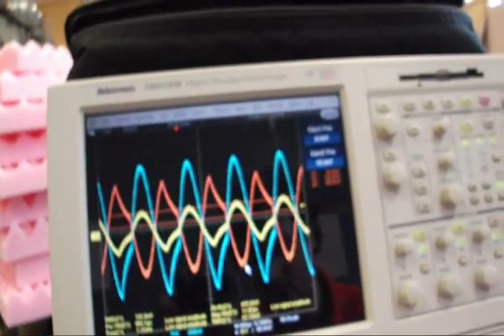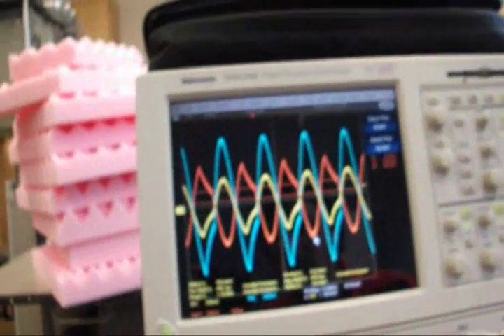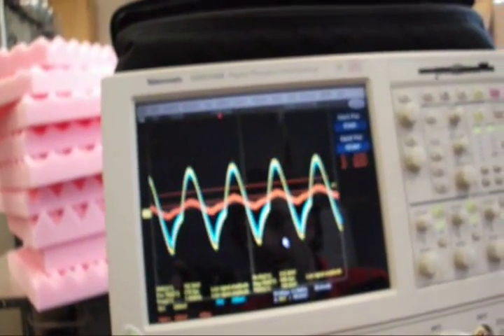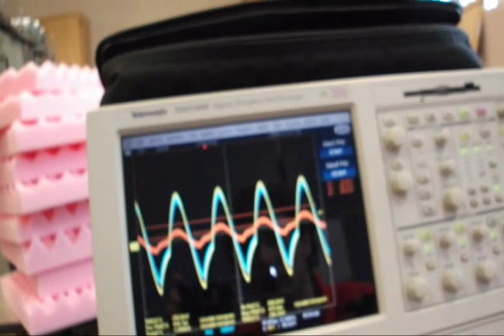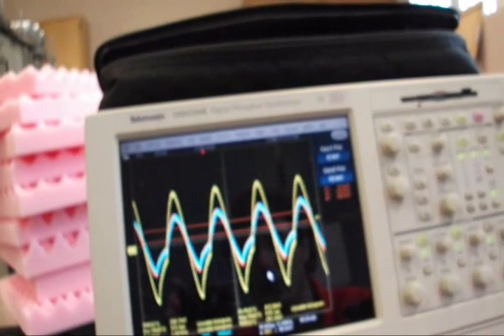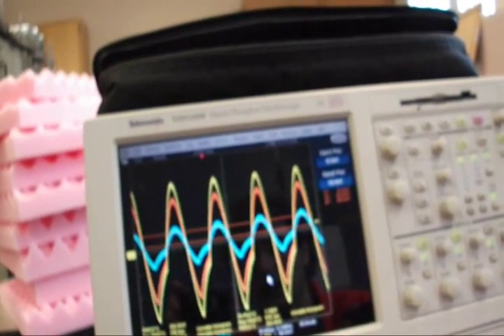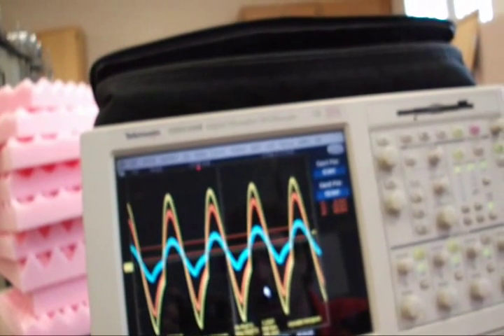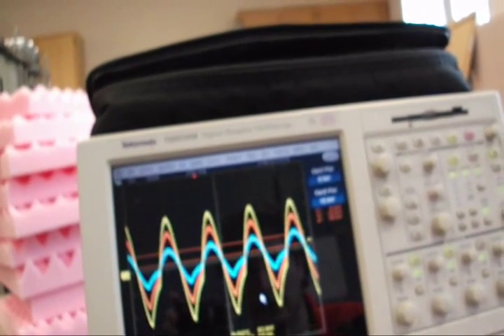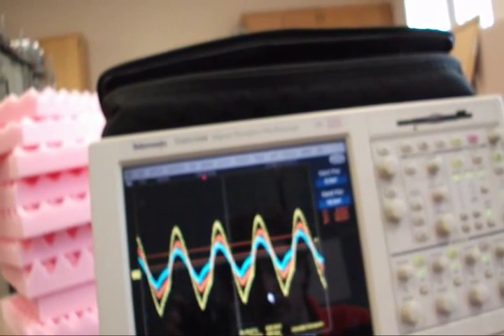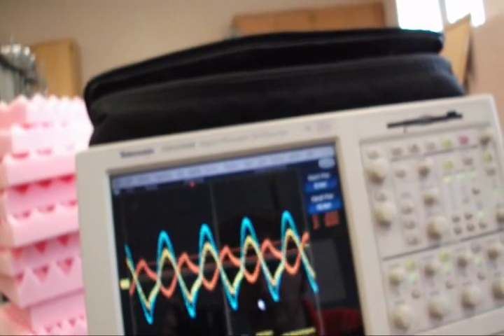If I were to hold the LVDT and move it in the opposite direction, you can see that the exact opposite is happening. We're at what you call null there, which is where the two secondary voltages are approximately the same and your core is at the zero position. But as I continue to move past null, I get a larger yellow waveform and a smaller blue waveform — the exact opposite of what I had earlier. And again, I'll move back, and it'll flip position.